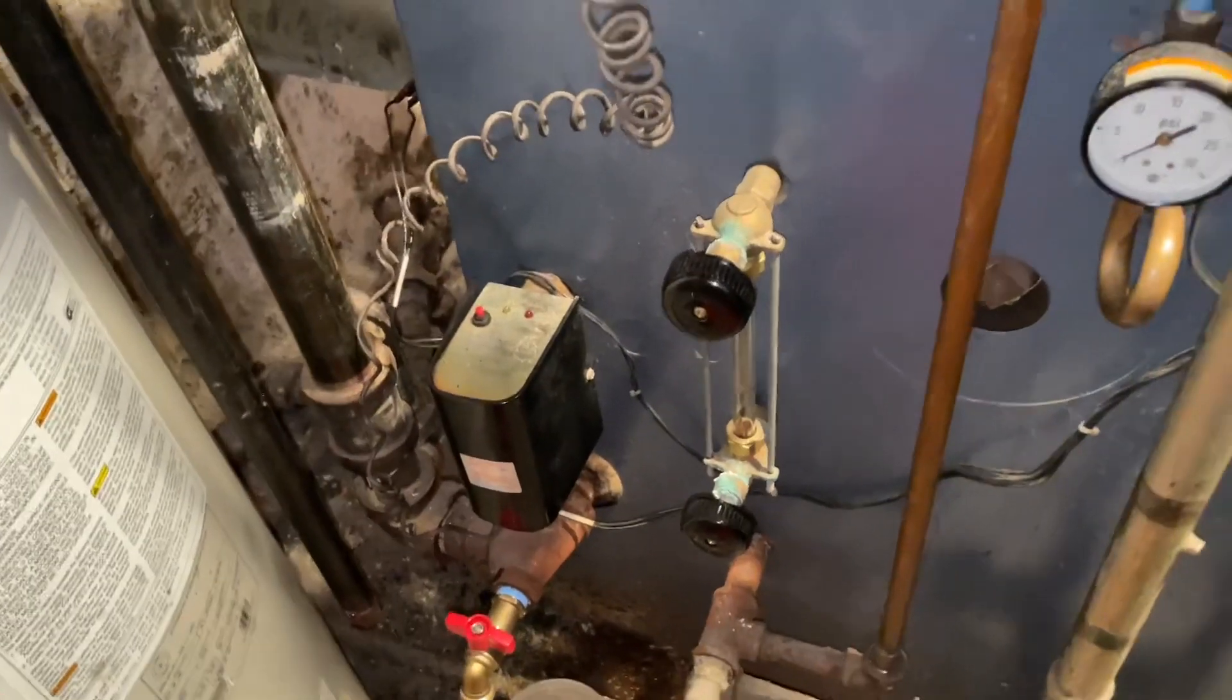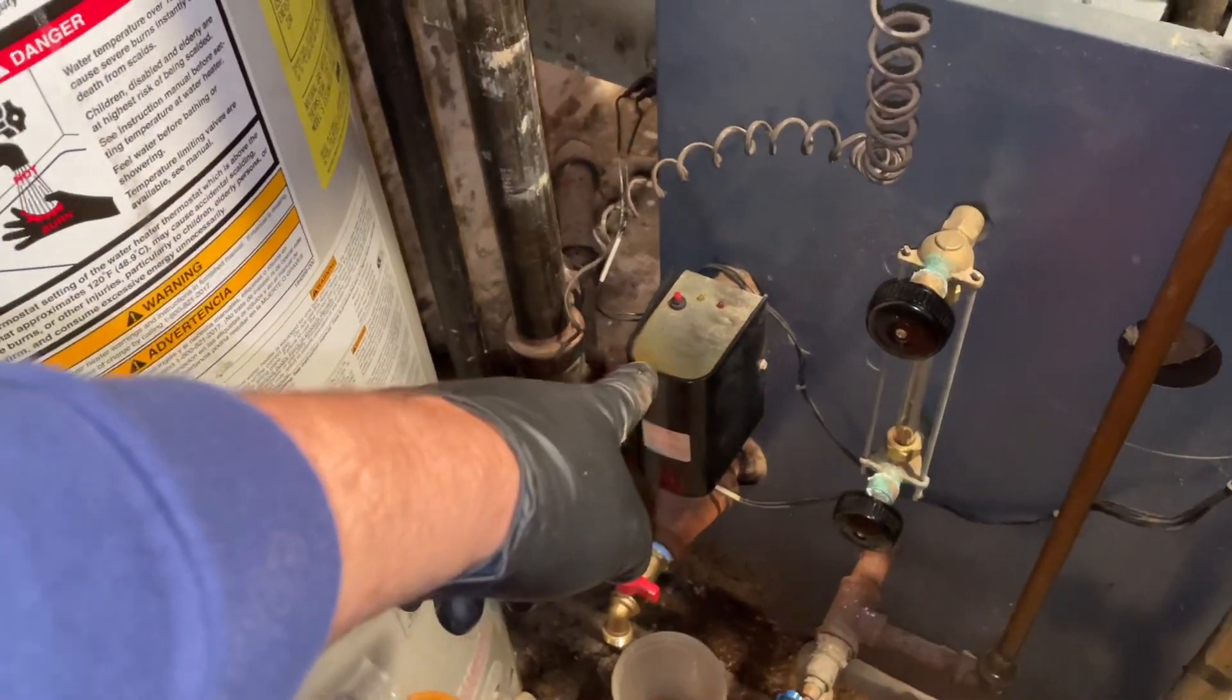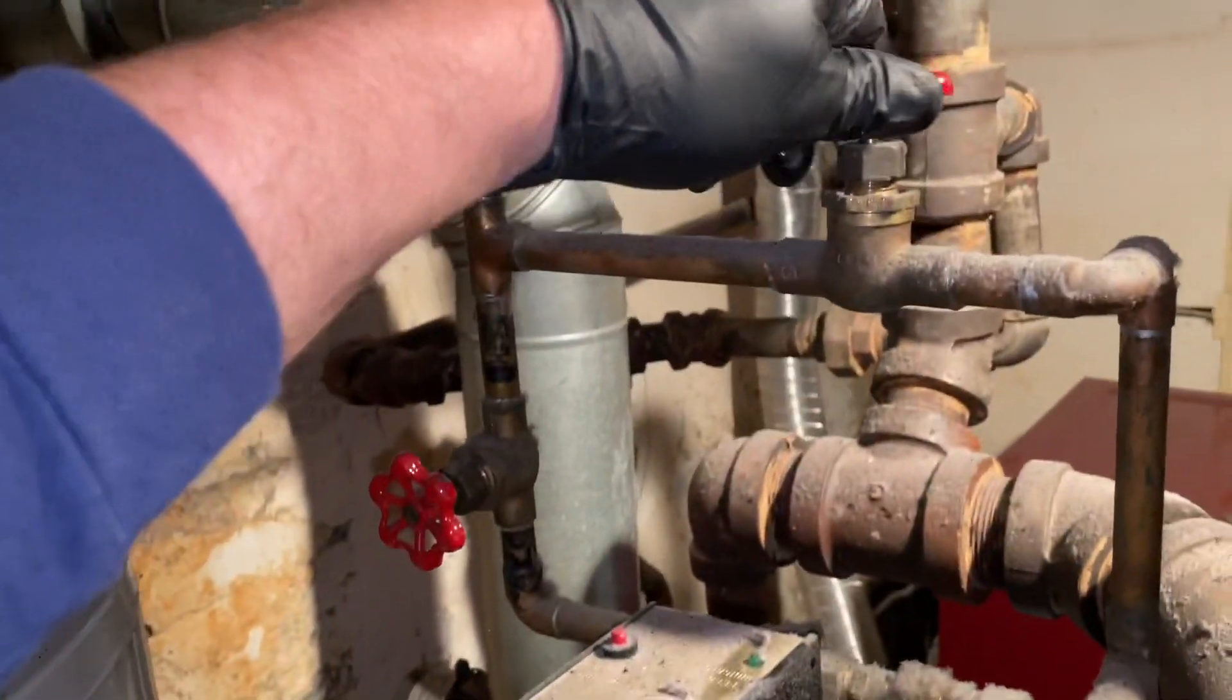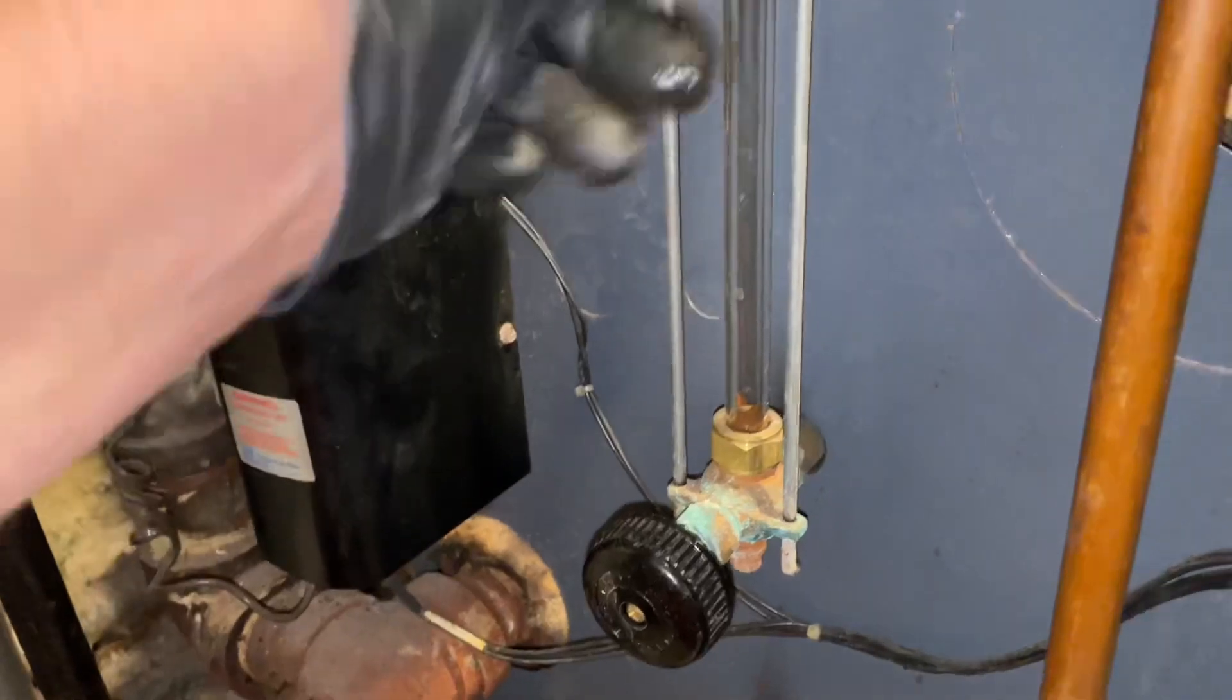All right, now she's got no water. So let's give her some water. This is called an automatic water feeder. It gets a signal from the low water cutoff and it starts filling up. This is a manual bypass valve to give it water. I'm going to watch that side glass rise up.